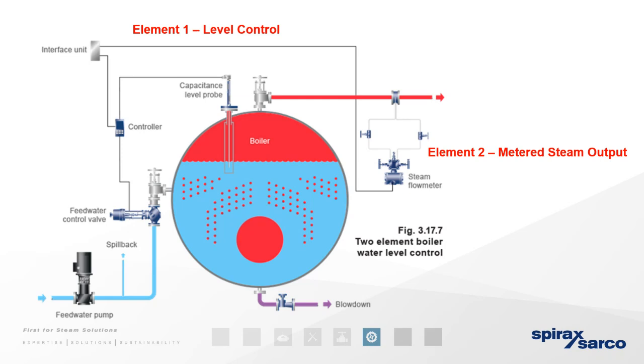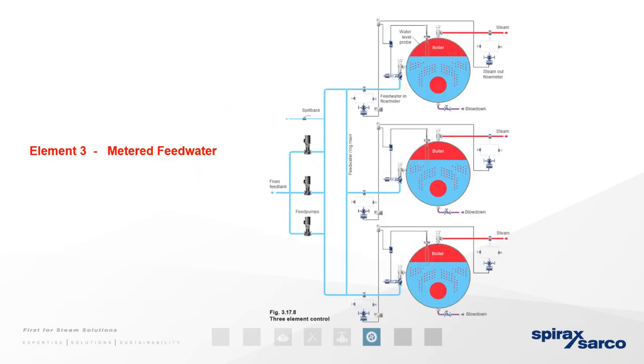No questions? Yeah. So 3 element, so metered feed water, tends to be more for when you have more than one boiler, several boilers at a time. So it's the same as 2 element, plus you end up with metered feed water. So you're metering the feed water into the system too. And this gives you a more stable, more efficient and better steam quality. Must have modulating supply to it though.